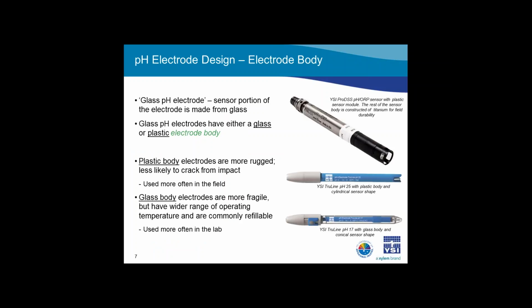The term glass pH electrode is commonly used, but this description is simply referring to the material used to construct the sensing portion of the pH sensor. Glass pH electrodes can have either a plastic or glass electrode body. Field electrodes typically have plastic bodies, as plastic body electrodes are more rugged than glass body electrodes. YSI offers both glass and plastic body electrodes for the lab, with glass electrodes having a greater range of operating temperature. Glass body electrodes are also frequently used in more challenging samples, such as very acidic solutions, where plastic body electrodes are not suitable.